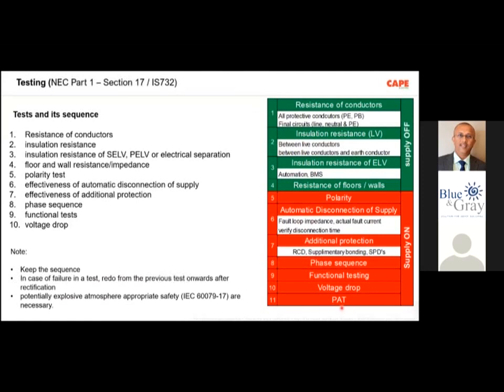PAT is, I would say, an 11th test, which is made mandatory in some countries. For example, in Australia, if you buy new equipment, before putting it into your electrical installation, you are supposed to do a PAT test. PAT stands for portable appliance test. Now, you must understand that not only the PAT test, all the tests are important. If you don't do all the 10 tests and do only the PAT test, you cannot ensure any safety. You have to do the entire set of tests.